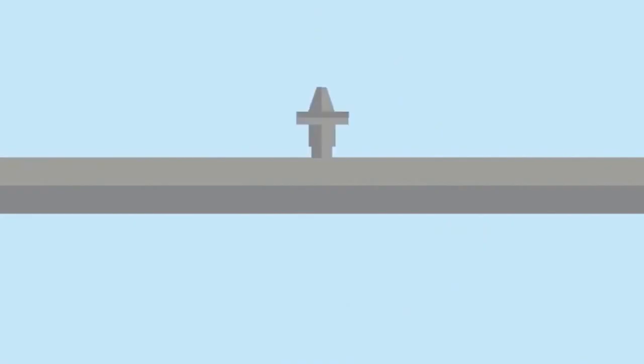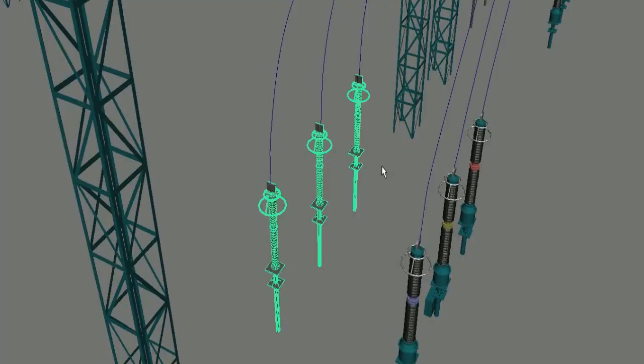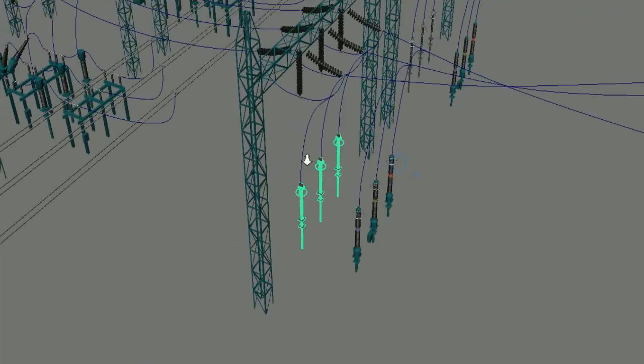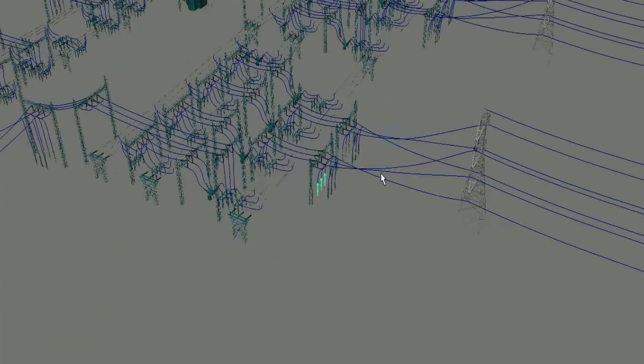This is similar to the situation where a fluid-carrying pipe consists of a safety valve, and when the fluid pressure increases, the safety valve throws out extra liquid and prevents the pipe from getting burst. After normal conditions arise, the arrestor recovers its rated resistance and gets ready for the next event.